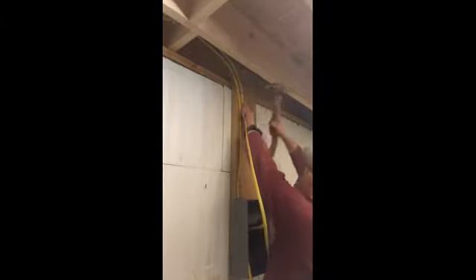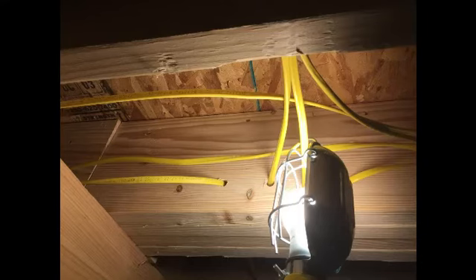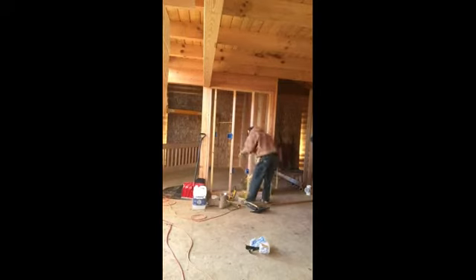So if you're going to have a ceiling that's going to be tacked up onto your floor joists in your basement, you don't want to run the wires along the bottom of the floor joists and just staple them up. You're going to want to drill through the floor joist, which is legal. It's all code. And you're going to run the wires, your circuits, through those holes, and that way it hides it from the ceiling, and your ceiling can be nailed up to the floor joists. Otherwise, your ceiling can't be nailed on top of wires that are stapled to floor joists. That's illegal, by the way.